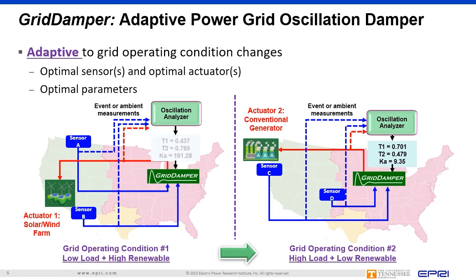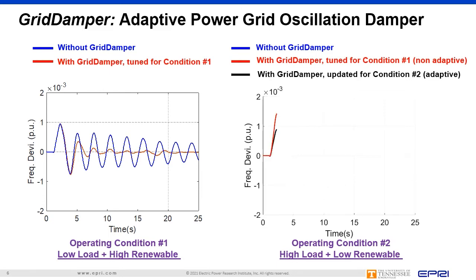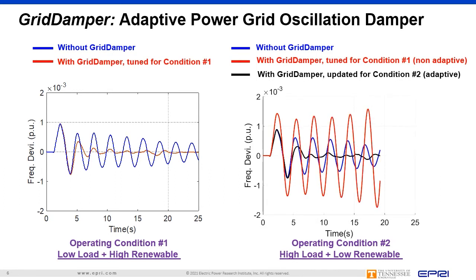It also changed the actuator from the solar and wind farm to conventional generators with updated control parameters. Although the controller optimized for condition 1 suppresses the oscillation quickly as shown in the left figure, its performance drastically degraded under condition 2 as shown by the red curve in the right figure. After the adaptive functionalities are turned on, the oscillation was quickly damped even under a very different operating condition, as shown by the black curve. This unique adaptive capability is available for all three types of oscillations.